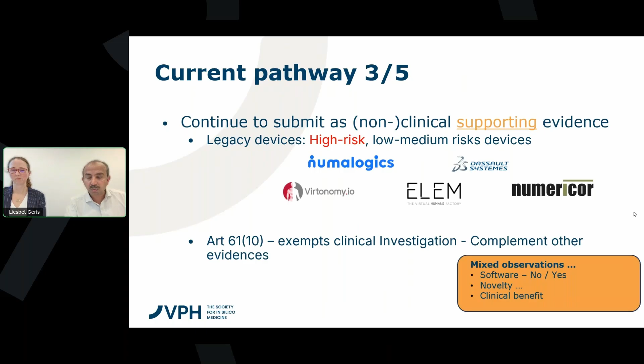So with that, the new evolution is on the orphan devices, where they are more open to accept that there will be limited pre-market clinical data. This means we may be able to open up the door a little bit to bring non-clinical evidence, by which I mean, in this case, in silico evidence can be considered as part of the regulatory dossier. This is officially listed in the MDCG guidance, which came out in June 2024. The condition for orphan is defined by the number of patients or individuals in the EU, like 12,000 individuals in the EU. But it's not just the prevalence of the disease or condition that qualifies your device as orphan. Rather, the condition should have either insufficient alternatives which don't work, or the device that you're proposing has a strong clinical benefit. With those criteria satisfied, your device can qualify as an orphan medical device.